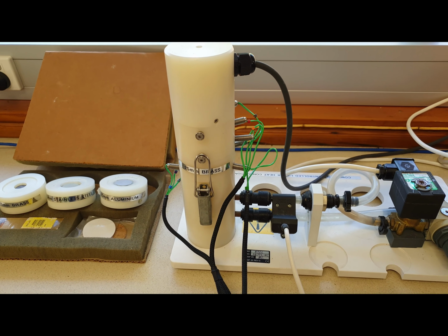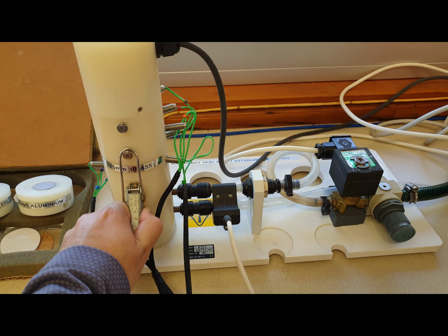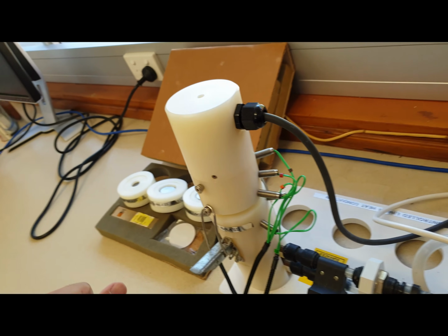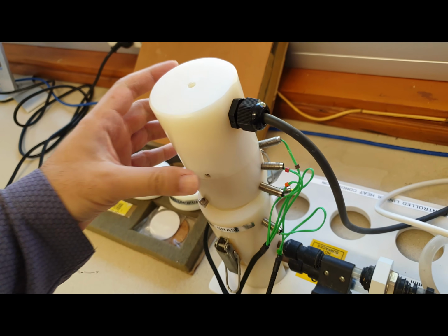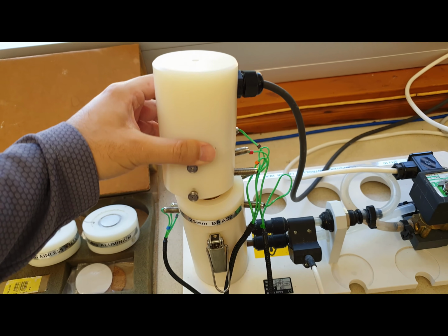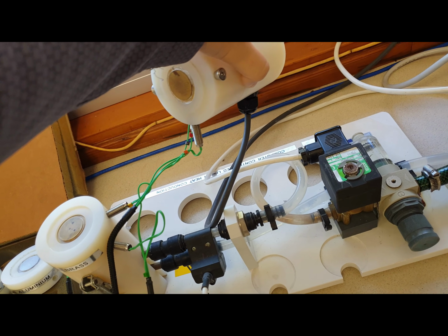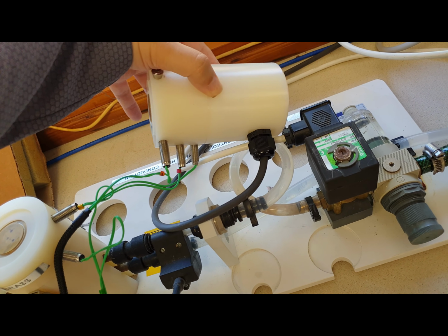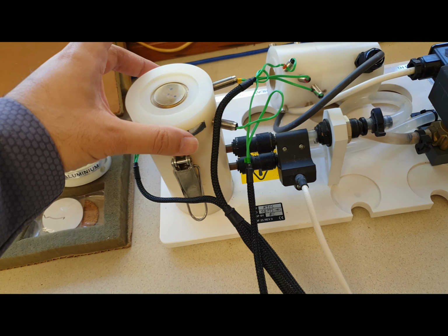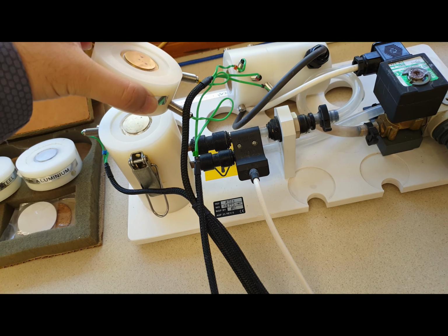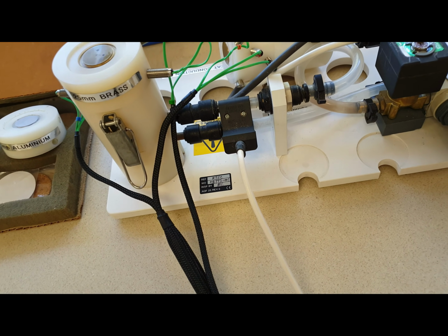To open and change the specimen, you are simply going to open the clamp at the front and at the back, and the heater part we are going to put aside. As you can see, we have 3 thermocouples attached to this part, so I'm going to put it there, and we can move this specimen. As you can see, 2 thermocouples are attached to this specimen.